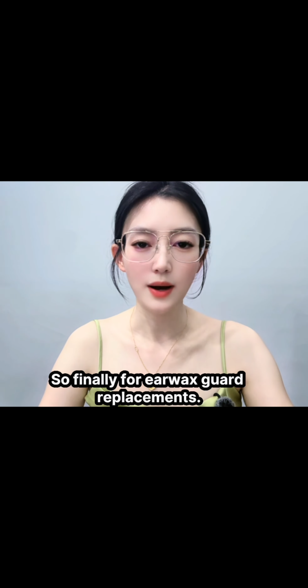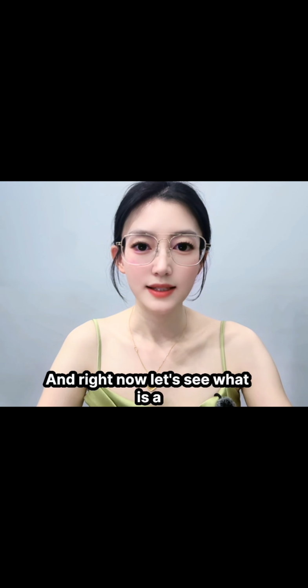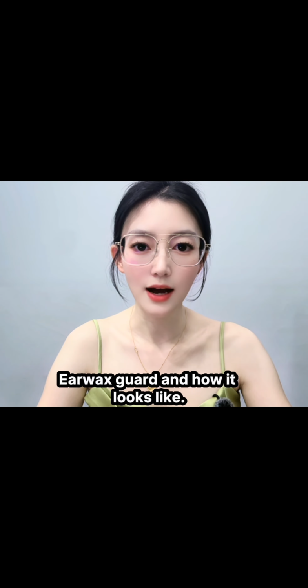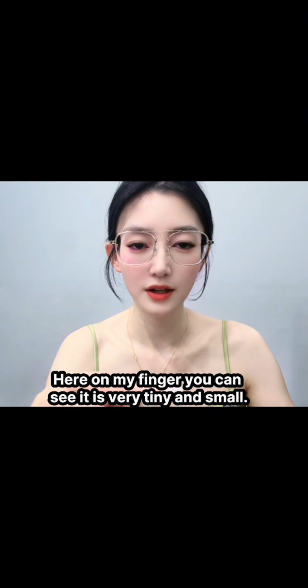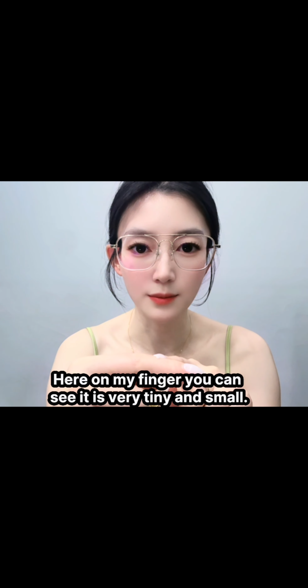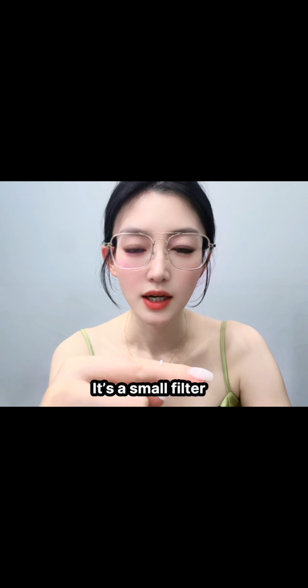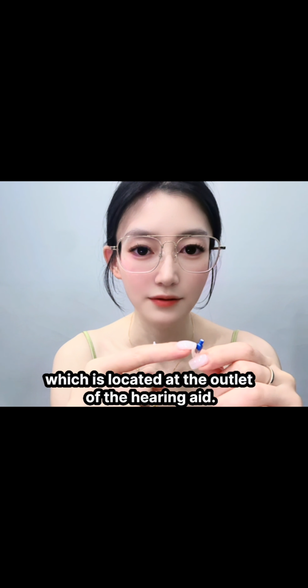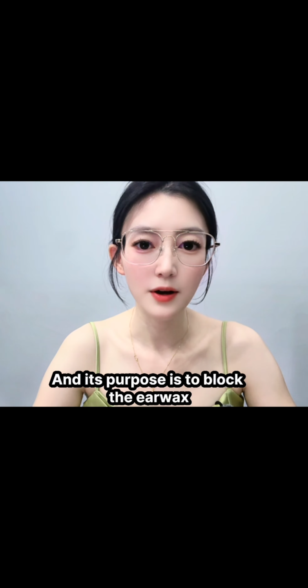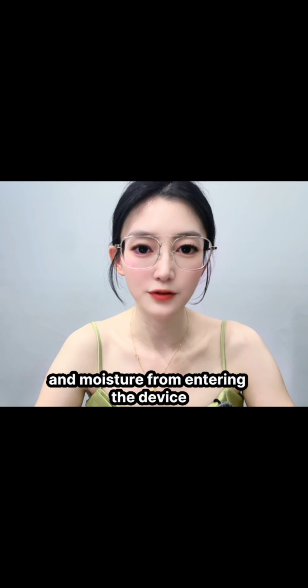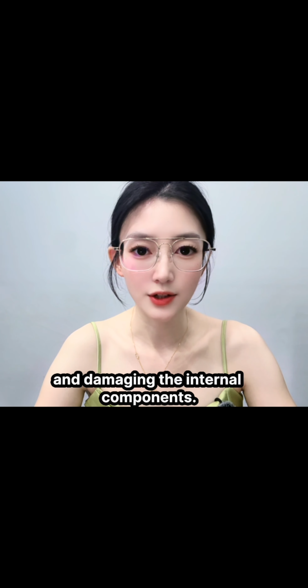So finally, for earwax guard replacement. Right now, let's see what an earwax guard is and how it looks. Here on my finger, you can see it is very tiny and small. The earwax guard is a small filter which is located at the outlet of the hearing aid, you can see here. And its purpose is to block the earwax and moisture from entering the device and damaging the internal components.